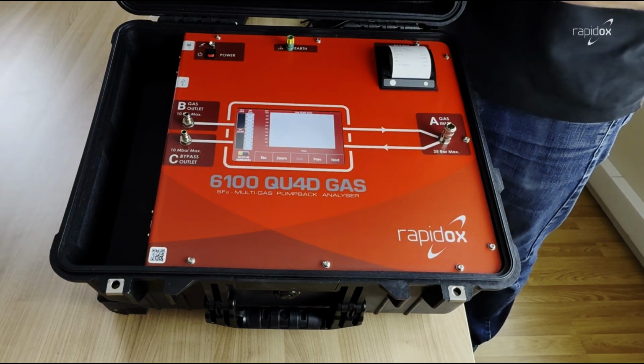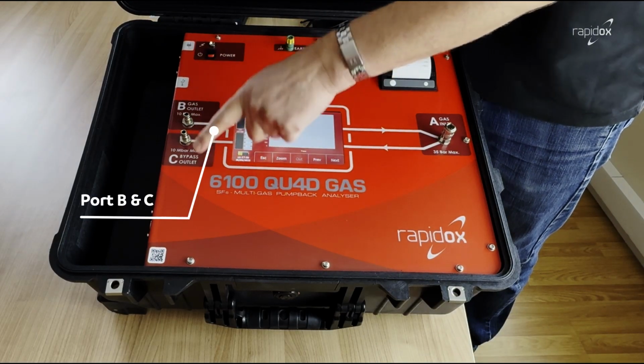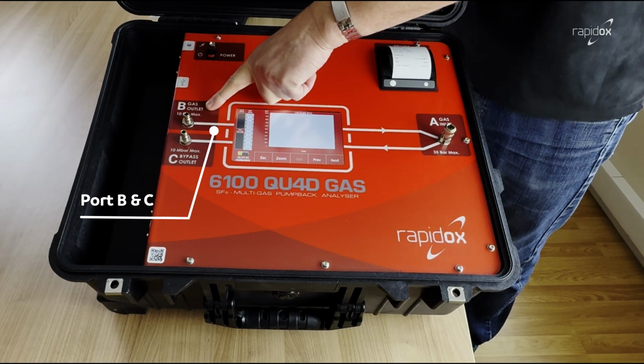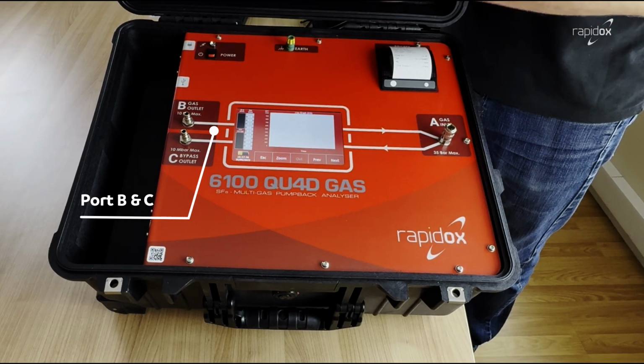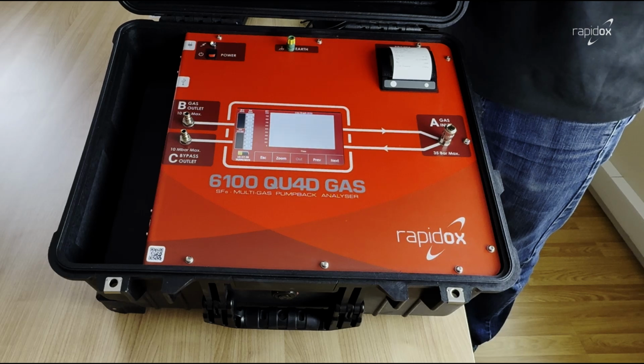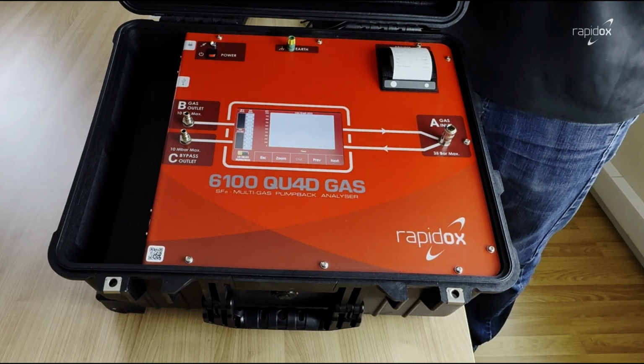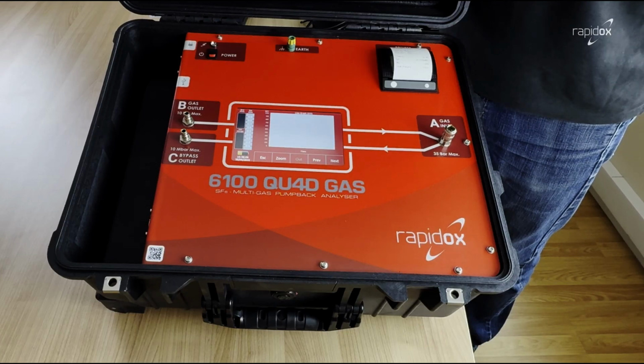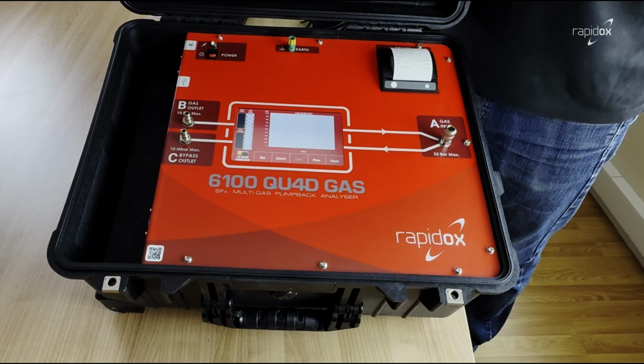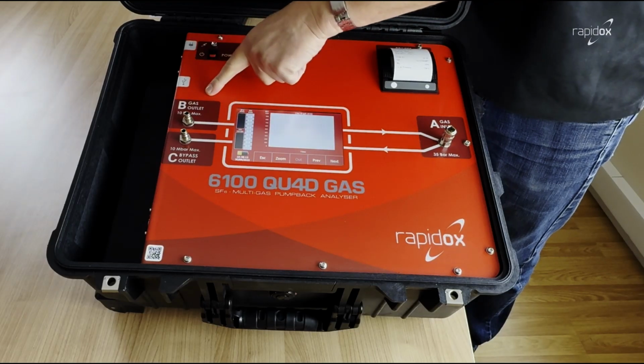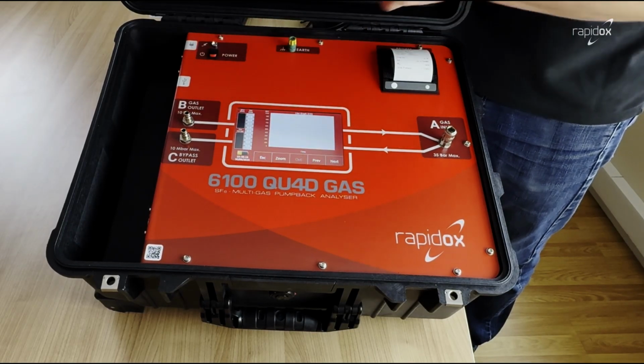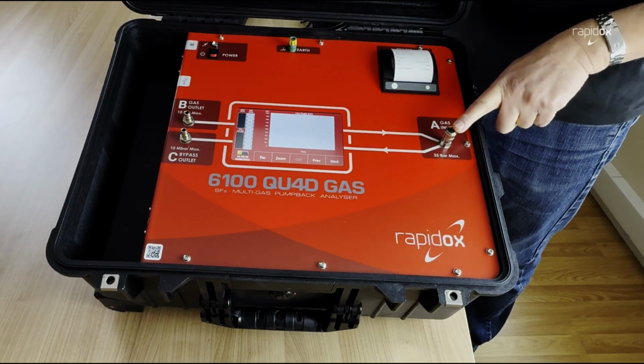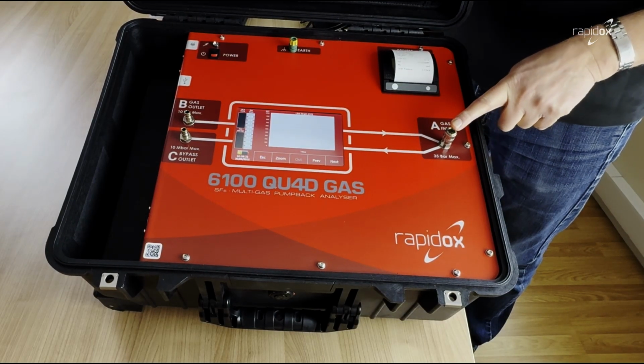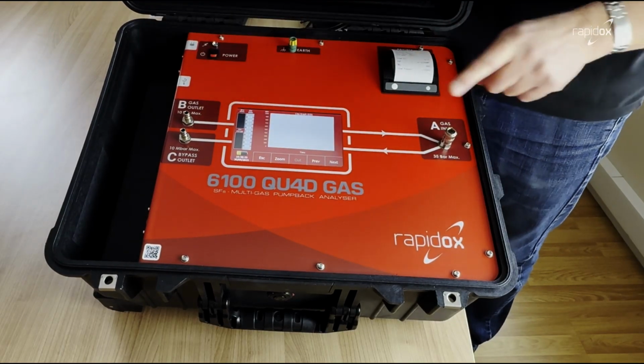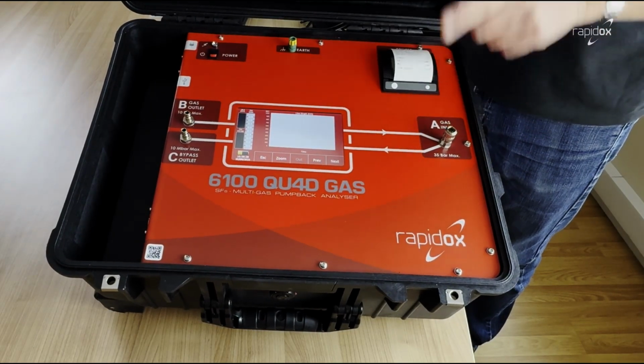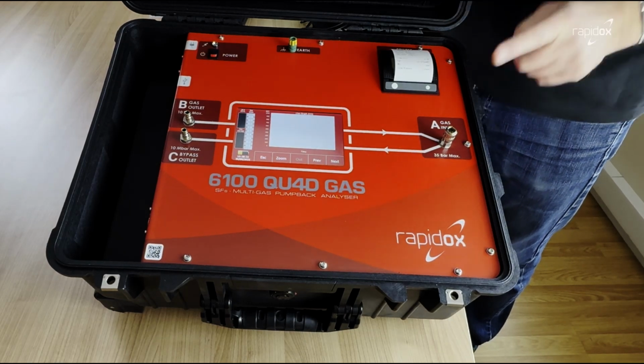Over on the other side we've got two other ports labelled B and C. Port B over here is used to transfer gas out into either a storage bag or a storage canister. This is used when you're doing line purging and you don't want any of the gas inside the line to escape into the atmosphere. So port B is a 10 bar outlet port, and it's the same size as port A, Rectus 21 series. However, this one is a male and this one is a female. This does mean that the same hose can be used over on port B and on port A.